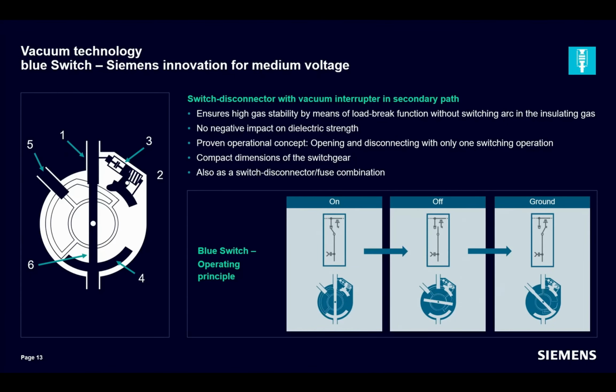Yes, Bernd, you know that Siemens is a pioneer when it comes to vacuum technology. In medium voltage applications, Siemens has used vacuum interrupters since 1977. It is a proven technology suitable for all switching applications. Now, moving away from SF6 and developing the Blue Switch, Siemens extended the use of vacuum switching technology also to so-called switch disconnector tasks. So what is a Blue Switch? Blue Switch is a 3-position load break switch with a vacuum interrupter in a so-called auxiliary path. It combines a make-proof switch disconnector, a make-proof earthing switch, and a vacuum interrupter in a parallel current path for arc extinguishing.